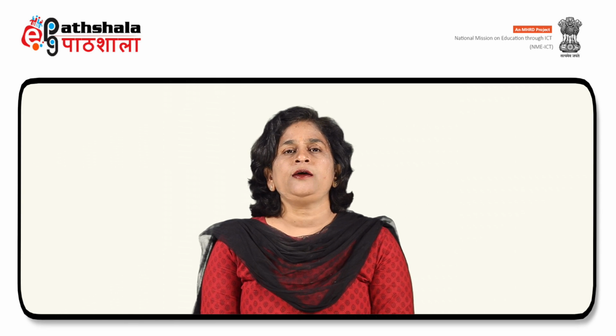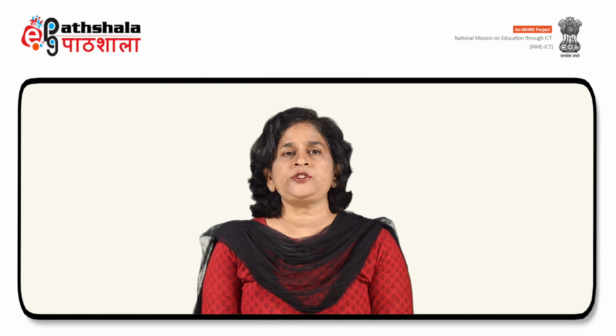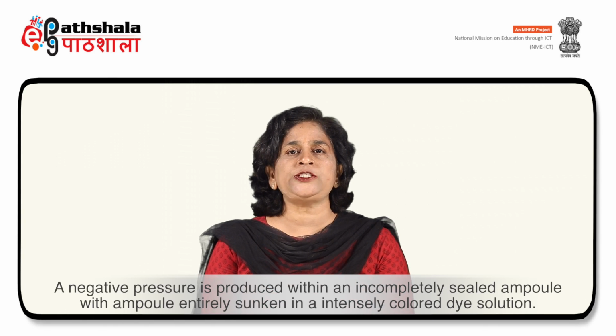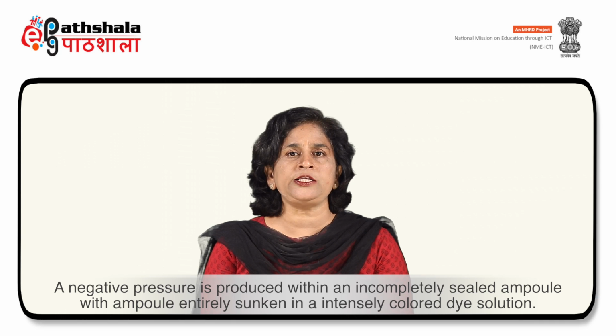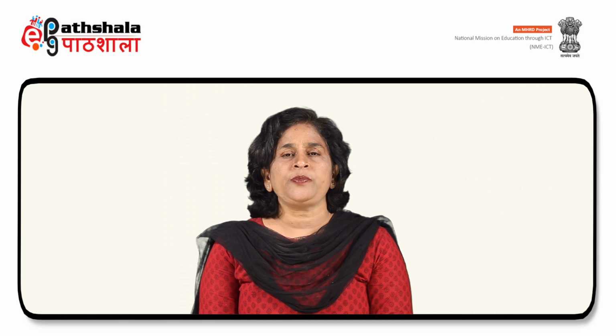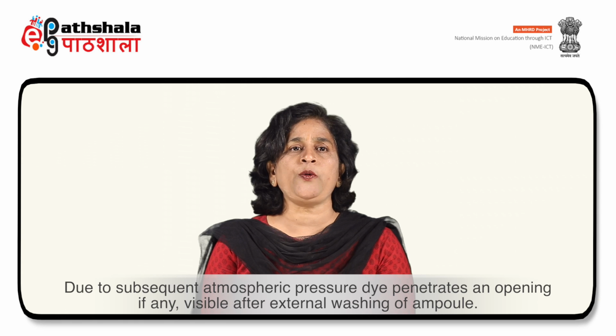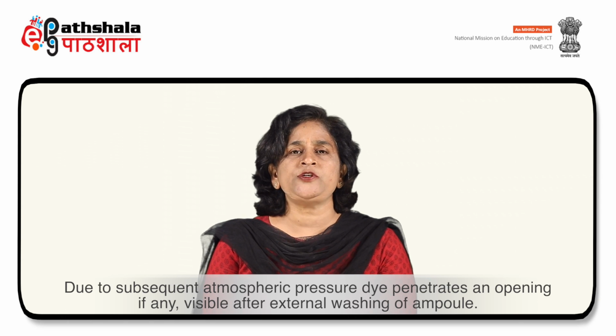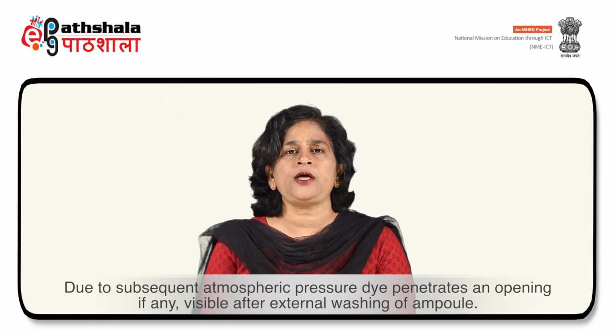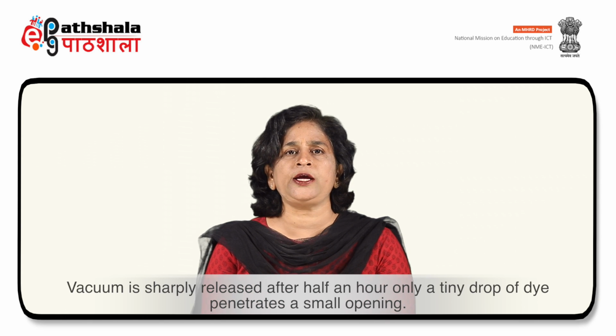Usually, leaks are detected as per a standard procedure in which a negative pressure is produced within an incompletely sealed ampule with ampule entirely sunken in an intensely colored dye solution, preferably methylene blue. Due to subsequent atmospheric pressure, dye penetrates an opening, if any, which is visible after external washing of the ampule. Vacuum is sharply released after half an hour. Only a tiny drop of dye penetrates a small opening.